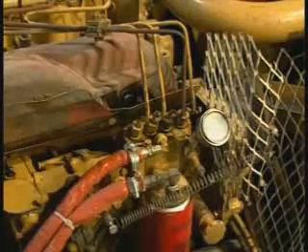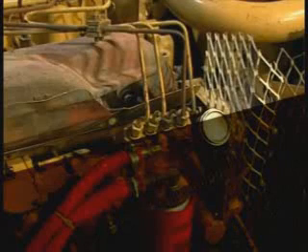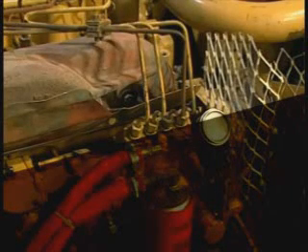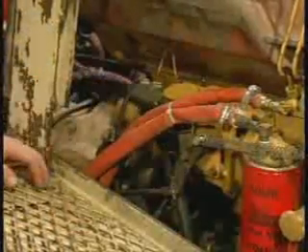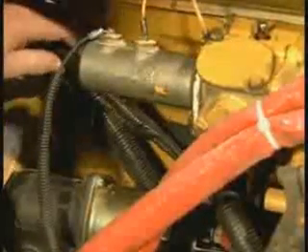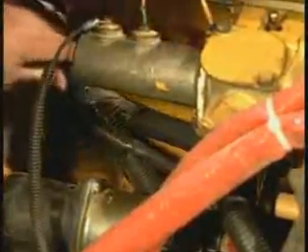Additional clamping would be required further back to prevent movement and to locate the fuel line further from the hot exhaust pipe. Although covered with a fire-resistant sleeve, contact with the hot exhaust could have a serious effect. Here we see the primary fuel lines located on the fuel filter and fuel pump. Above these, we see the OEM metal fuel lines. Although not required to have additional guarding, they must be maintained to prevent fuel leaks. It's important that fuel lines be separated from the electrical wiring and protected from damage in ordinary use. Electrical wiring must have adequate mechanical protection to prevent damage to the cable.